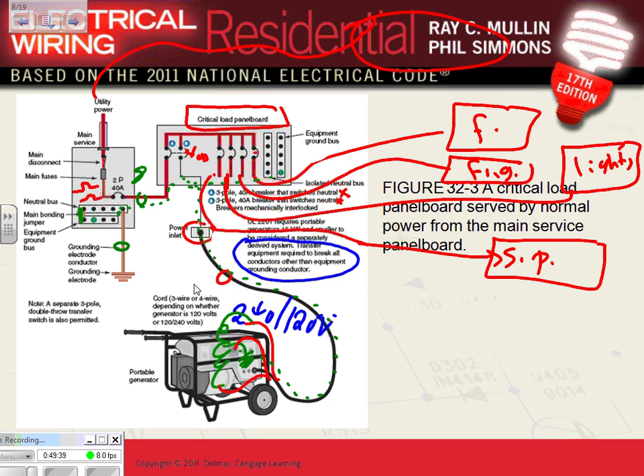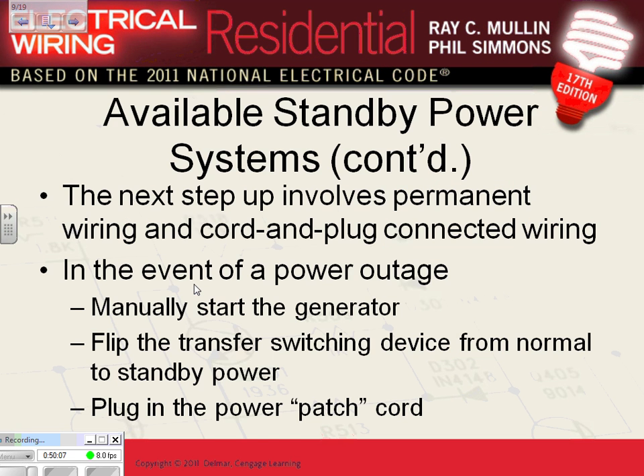This rule, if you guys read through this junk here, it's okay, you have to do it for 15 kW or less. 15 kW portable or less portable generators, that's how we do them. Portable, they have to be portable too. You see the word portable? We're moving it. Do I have to drive a ground line from here to the ground? No. Any question, guys, about this? Any question? So that's how you do it for residential.